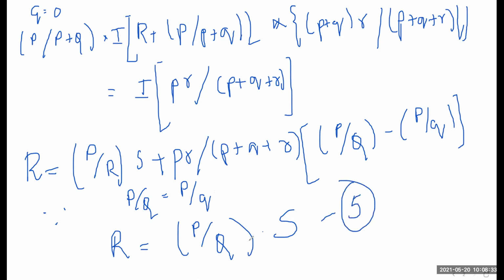The motto of this equation is that for obtaining perfect results, the arms ratio should be maintained equal, and the thermoelectric EMFs that are induced here sometimes need to be checked when taking the readings. That is important, because when you are using the Kelvin double bridge, you have to check the readings also, by changing the polarity of the connection. Therefore, the unknown resistance value can be obtained from both the two arms.